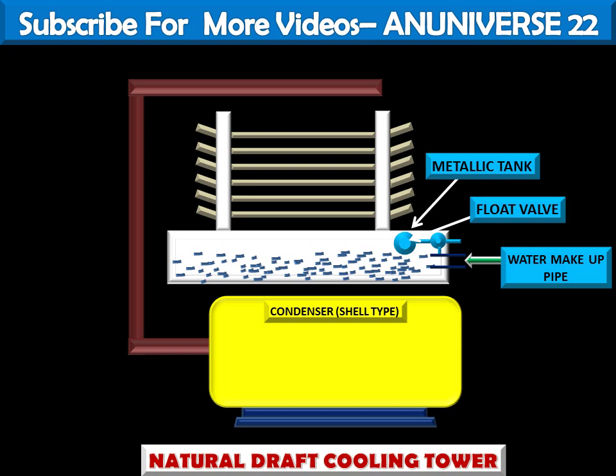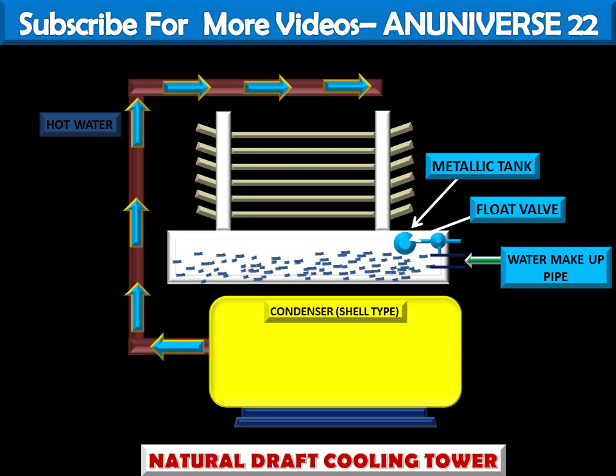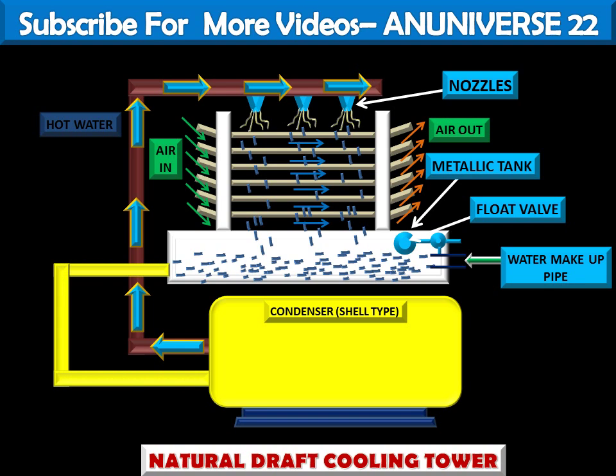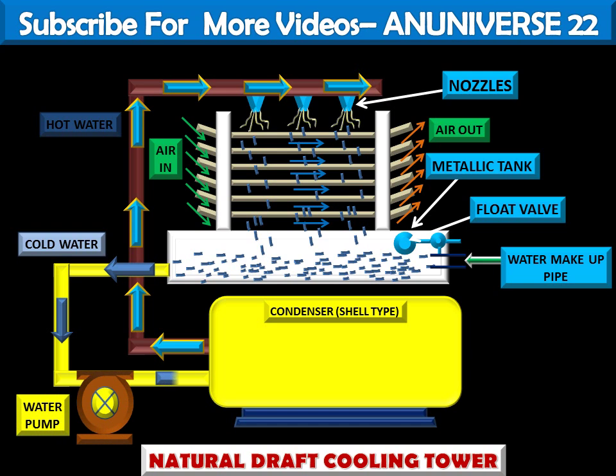This is the pipe connection. From the condenser, hot water is supplied to the spray header. From the spray header, water passes through the spray nozzles and falls into the metallic tank in the form of fine droplets. Air enters into the tower from the sides, passes through the water droplets, and exits out. The cooled water is then supplied back to the condenser with the help of a water pump.